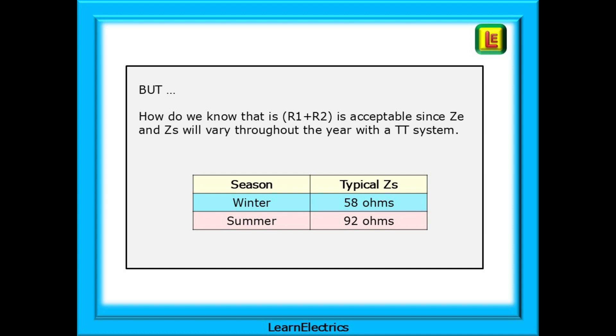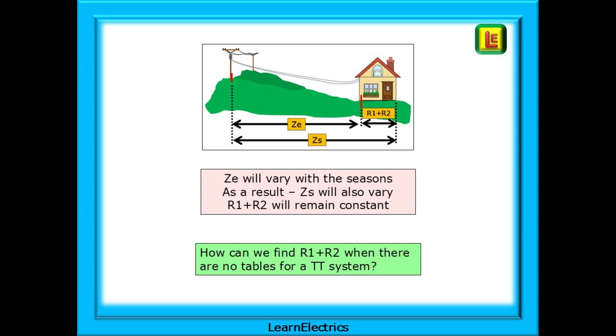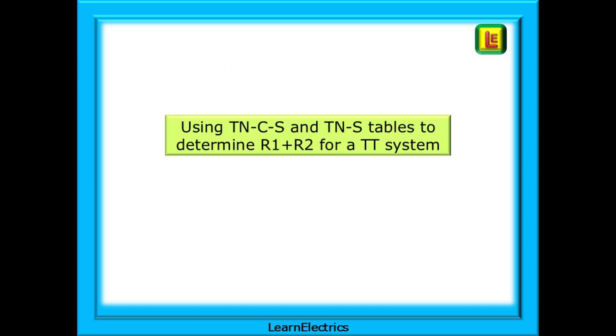We can measure R1 plus R2, but there are no tables for maximum ZS for different circuit breakers in TT systems. Typically, ZS values will be lower in the wet seasons of the year and higher in very dry seasons. It is the outside part that is changing. The inside wiring will remain as an almost constant resistance. So how can we find an acceptable R1 plus R2 when there are no tables for a TT system? We can use the TNCS and TNS tables in the books to determine a usable R1 plus R2 for a TT system.